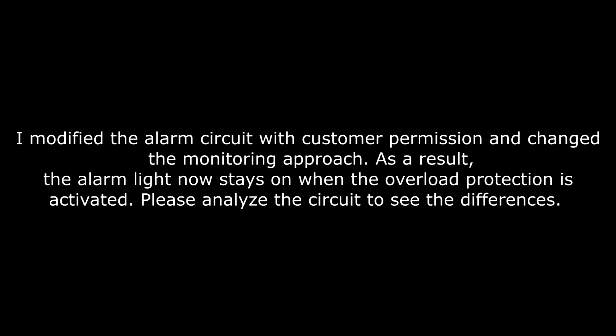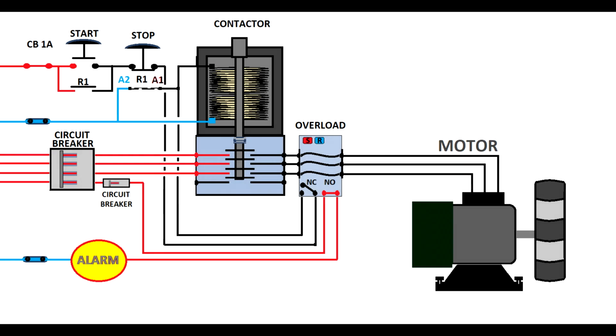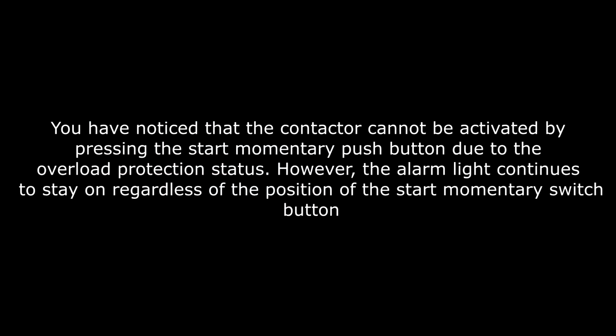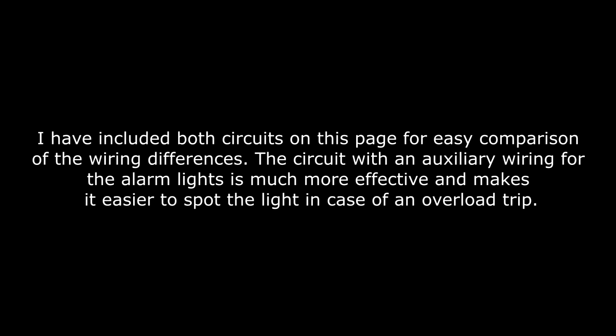I modified the alarm circuit with customer permission, and I changed the monitoring approach. As a result, the alarm light now stays on while the overload protection is activated. Just have a look and try to understand. I changed the wire configuration, and now the alarm light has its own supply, and that will make the customer see it faster. See, now I'm pressing the start switch, and regardless of the start switch status, the alarm stays on while this overload is activated. Because you notice that the contactor cannot be activated by pressing the start momentary push button due to the overload protection. However, the alarm light continues to stay on.